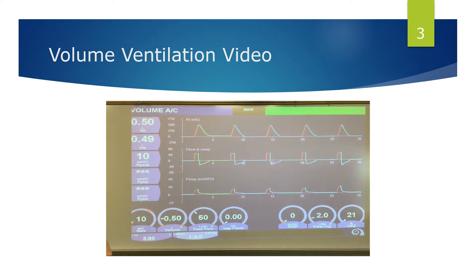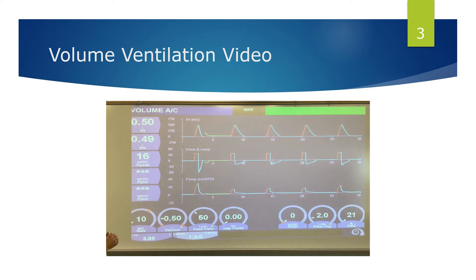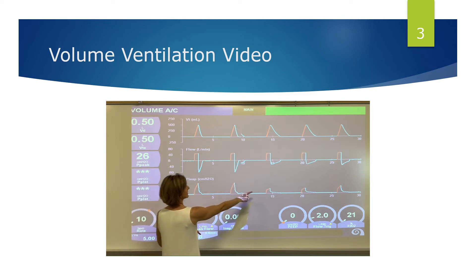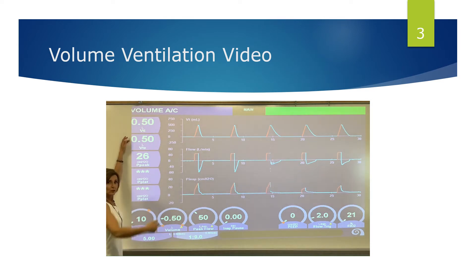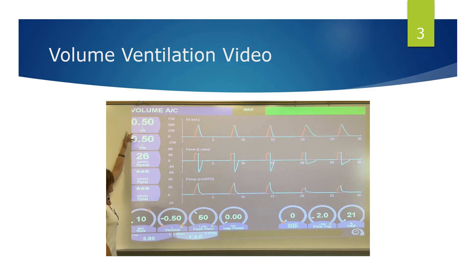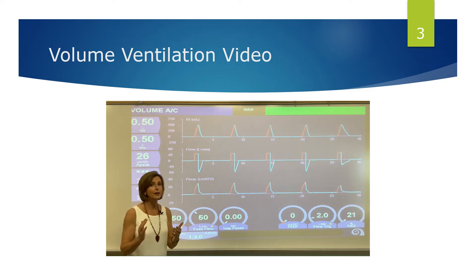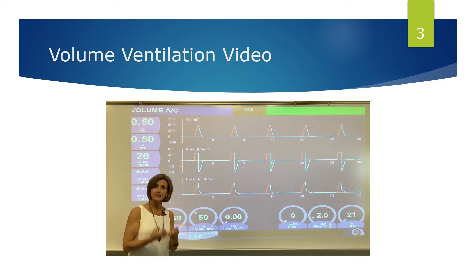As I decrease compliance — see how that pressure has increased? With a decrease in compliance we're still pushing that same tidal volume in, but the peak pressures have increased to do so, because it takes more pressure to drive the same tidal volume into a stiffer lung.